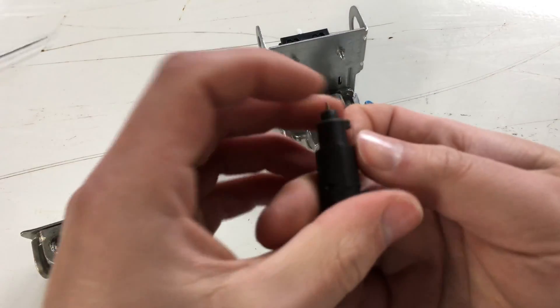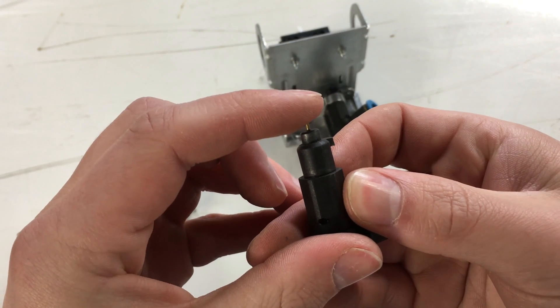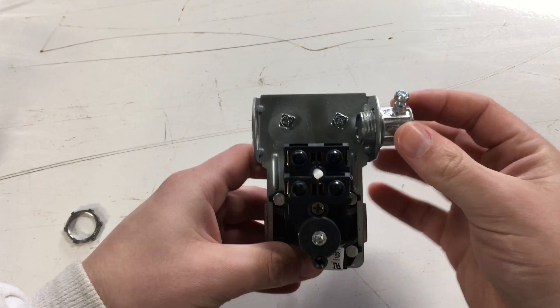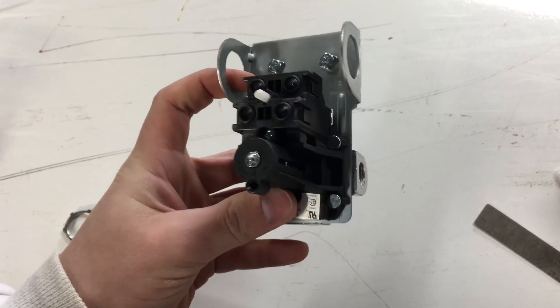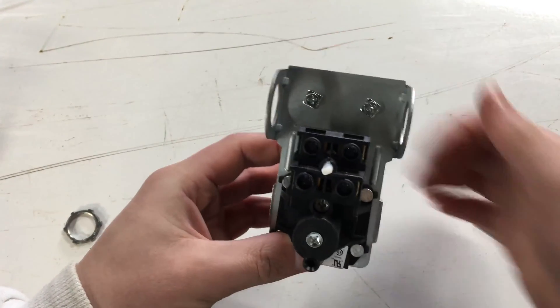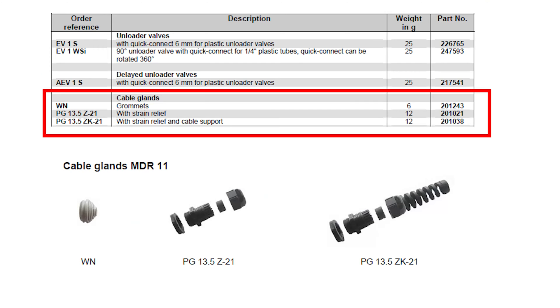Here is the little needle valve — it doesn't take very much pressure at all to push it in and out. The two ears with the holes on the frame are for attaching electrical conduit fittings. One side is for the outlet or line power and the other side is for the motor wiring. It has two ground screws for grounding the wire from the line and for the motor. There are also rubber grommets that go on these holes for wires to pass through, which I assume is for when you're not using conduit and just using flexible wiring.